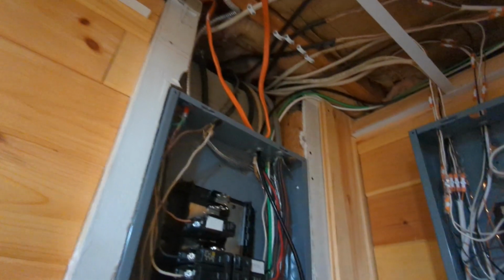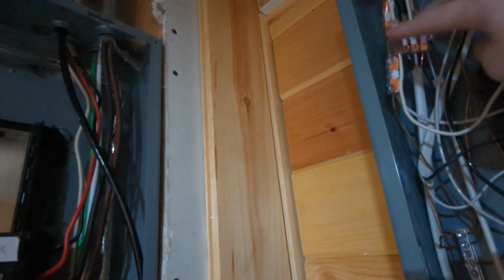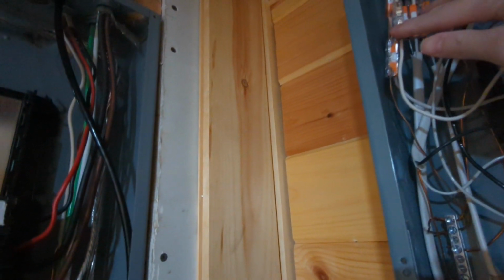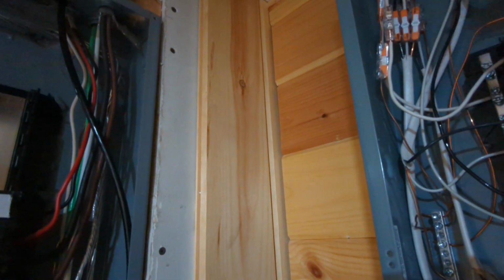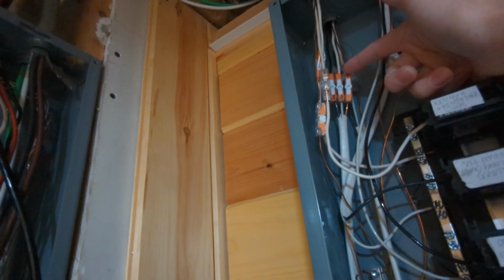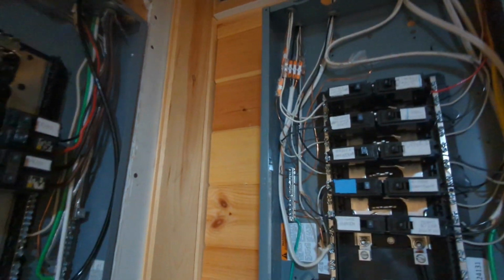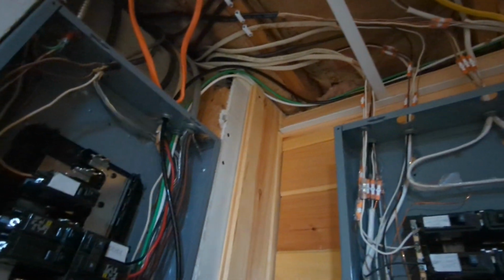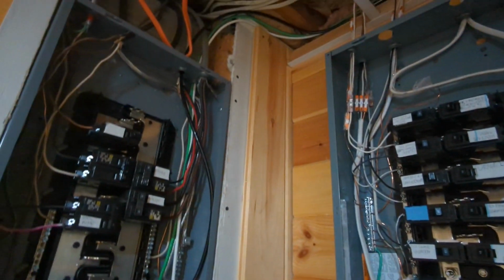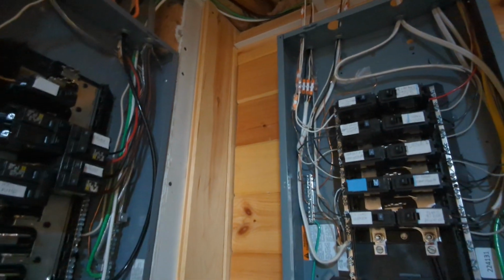Instead of those wires coming into this panel, I've had them extended with some of these extension connectors. These are similar to Wago style connectors. You can lift up this orange tab, and then you can pull out the individual wires. Those connectors are UL listed. I do believe code also requires these wires to be pinned or mechanically secured, so I cannot pull on those wires, and they're held in place. So my only option was to extend them to connect to these breakers.